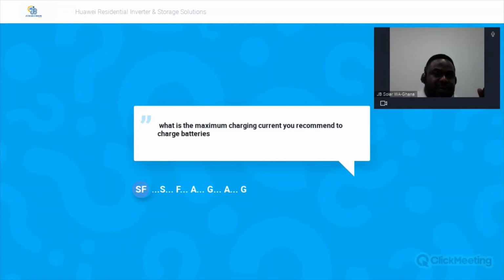Saeed, what is the maximum charging current you recommend to charge batteries? The Huawei system itself recommends two kilowatt for charging the batteries, but it gives you the opportunity to go for a maximum of 5. Okay, the recommended is 2 kilowatt, but it gives you the opportunity to go for 5, and it will not disturb anything at all. Not that the 5 will damage something or destroy something, no.